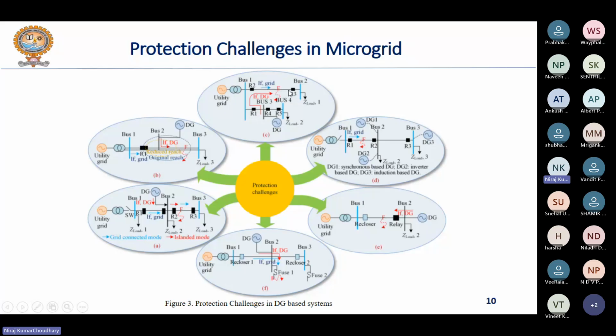But now, what is the problem in this case? You have a DG connected on the other feeder, where the fault has not actually occurred. So along with the utility grid, you have a DG connected to the system. If the fault F occurs here, then there will be two sources for this fault, one from the utility grid side, represented by IF grid, and another from this DG, that is IFDG, the fault current supplied by the DG. So what will happen if this IFDG exceeds the pickup current of relay R1? This relay will sense this current as a fault, and ultimately your healthy feeder may get isolated from the system. So this is one case of maloperation of the relays, that is, false tripping of a feeder on which the fault has not actually occurred.